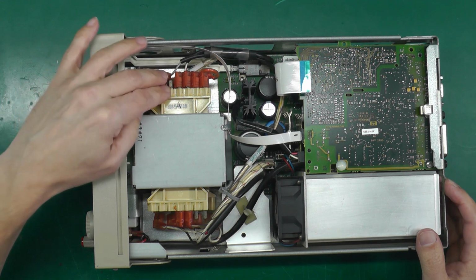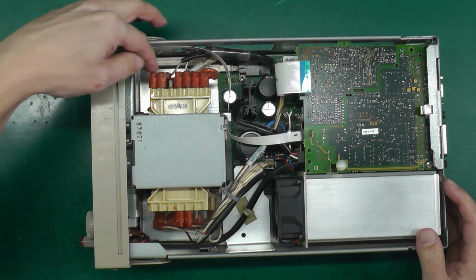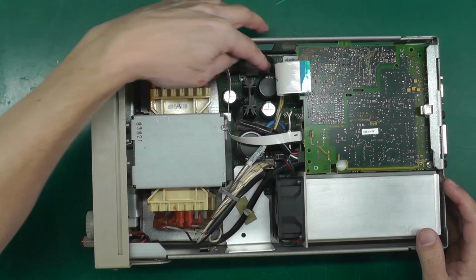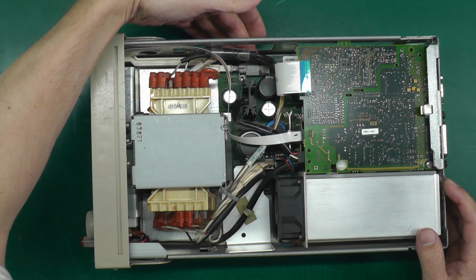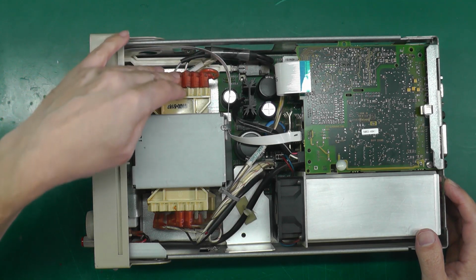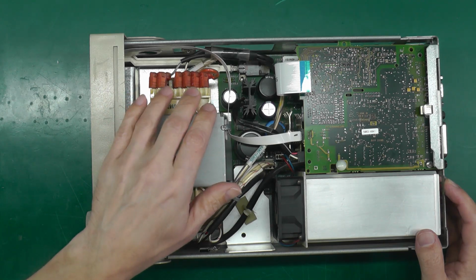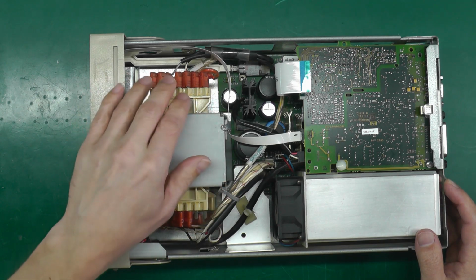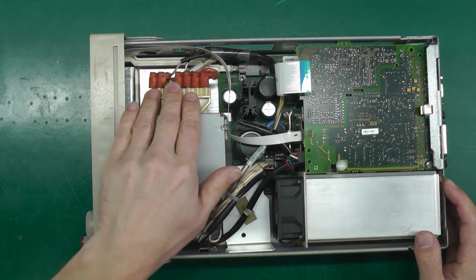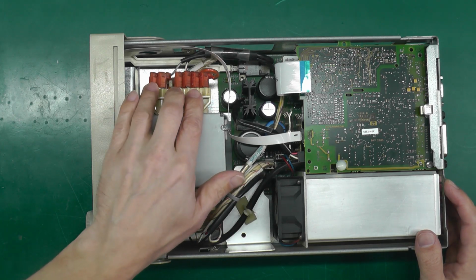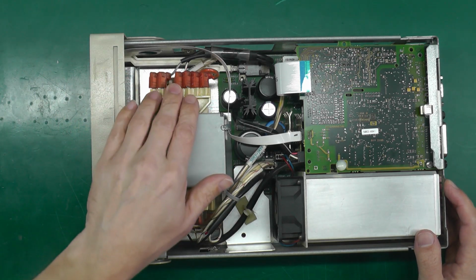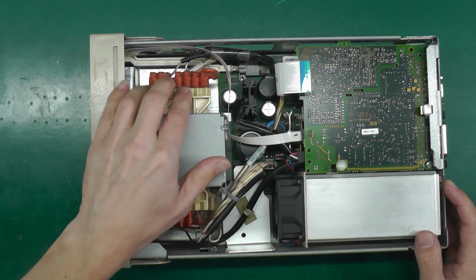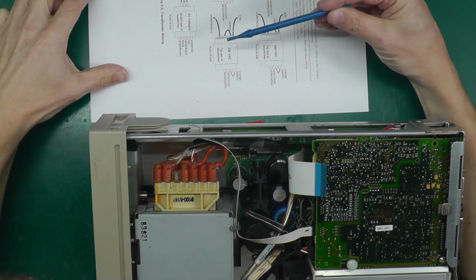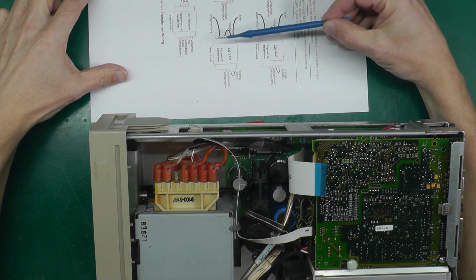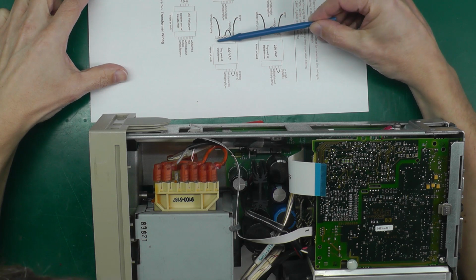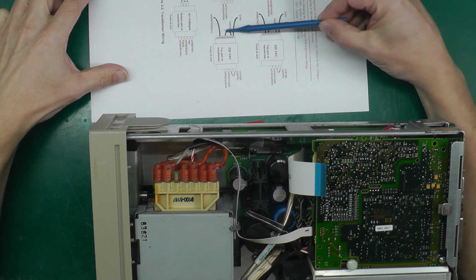terminals here. You can see that we've got some wiring coming off a couple of the terminals down onto the PCB where the main switch is, so we're obviously in the right vicinity there. So we've got a service manual. It does say how to set up the incoming AC, so we'll take a look at that now. We'll verify it is set up for 110 or 120, something like that, and we'll work out how to change it to 230. Which is this one here, which has 2 series windings there, and obviously with this configuration of the terminals there. So I'll go away and do that now.